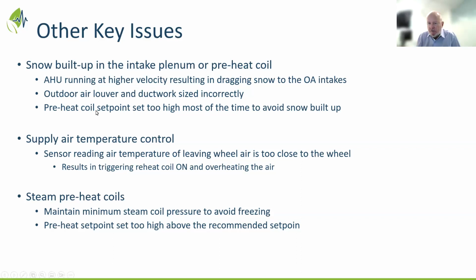Yeah, I mean, this is a big deal, right? This was the big issue at Alberta Children's, wasn't it? Yes, we had snow build-up. We just had to keep the preheats running, and that again kills the wheel. Between the different hospitals and air handling units you looked at, presumably a number of air handling units don't experience that issue. Were you able to document the differences between them? Was it longer spaces between the intake louver and the coil? Was it the velocity of the air coming through? Like, were you able to see, we don't have a problem with these units, but we do have a problem with these, as a kind of design instruction, if that makes any sense?